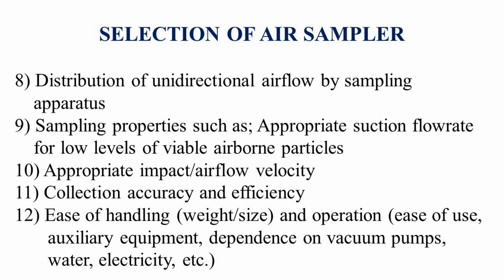Tenth is appropriate impact and air flow velocity. Suitable air flow velocity is necessary to sample and stick biocontamination onto the agar plate; it should not be too high or too low. Eleventh consideration is collection accuracy and efficiency. The sampler should collect the exact sampling volume with efficiency and should not modify results by means of damage to bioload or breaking of bacterial clumps.